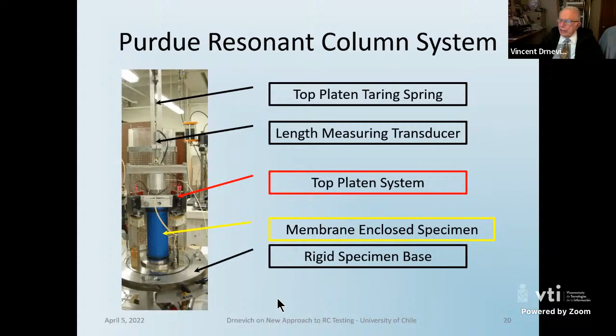So this again is the Purdue resonant column system. We're showing you here a taring spring to take the weight off, to counterbalance this weight here. And there's a length change transducer which measures the specimen length change during a test. This is looking down on it. There's a top platen system. You can see a magnet here, another one here, and those magnets have their gaps in the coils. There's another set of coils over here and two more magnets at the top.